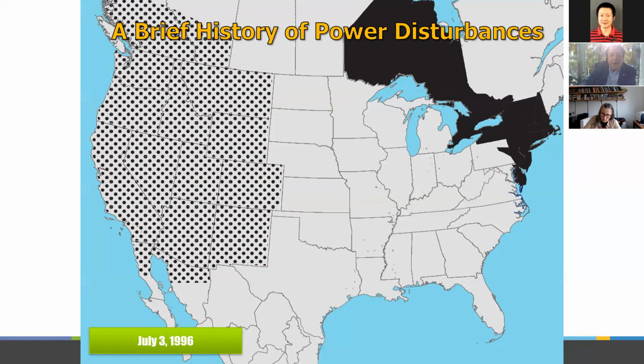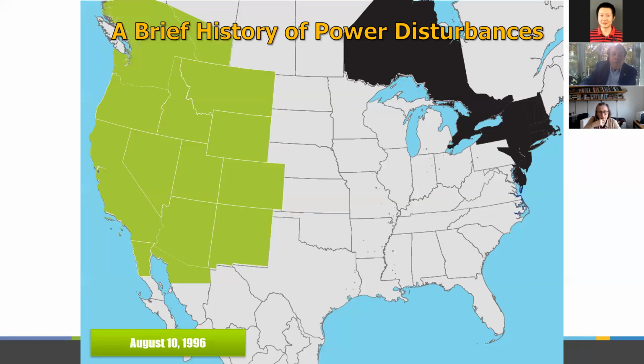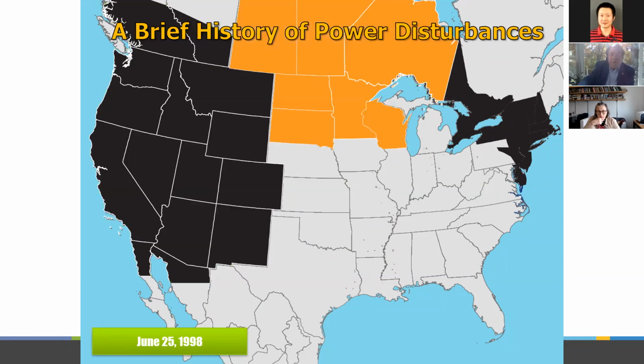And unfortunately, the misoperation of the relay happened again. But the operator had 30 seconds and he knew it was a misoperation and restored the line, and the blackout did not occur. But before the ink was dry on the letter that went to the president, another event occurred. 100-degree day, it was quite hot. Several lines overloaded and sagged into trees, and we had a similar area covered by an event. So I remember well the emphasis that, hey, the markets are not causing these problems. This was temperature and overload conditions.